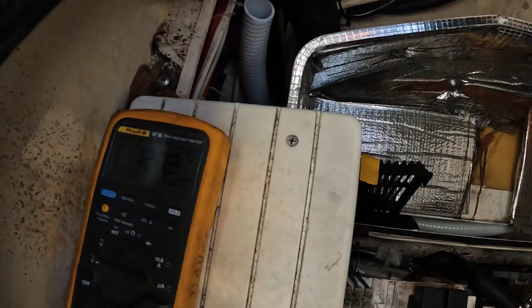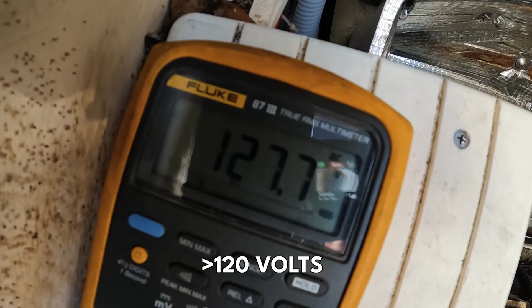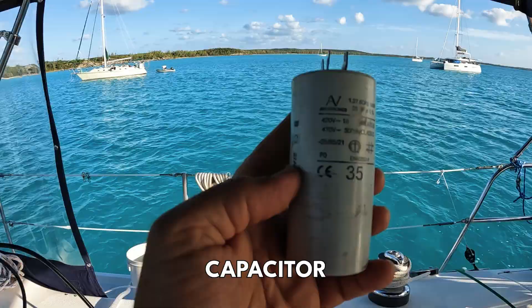Or the capacitor is going out and is just very inconsistent on when it gives you 120 volts. Okay, a few hours later and we have it fixed—just changed out the old capacitor and put a new one in. We carry a spare capacitor, as well as an oil temperature switch, a relay, spare zincs, and belts. Every time we've had a problem with the generator, the easiest fix is just to replace a part. Have the spare parts, replace it, fixed. So lesson learned: we're going to restock all of our spare parts since we've gone through at least half of them, and then we're good to go.